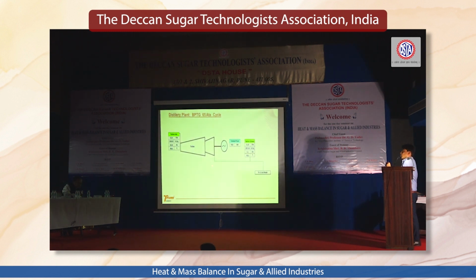So during off-season scenario, when we go for seasonal operation, we extract the maximum amount of steam, almost 80 to 90%, in controlled extraction. The flow to the cooling condenser is only 10 to 15%. So 70% of the latent heat of the steam water is not sent to the cooling tower, we use it for the process. So with respect to seasonal operation versus back pressure operation, efficiency is always on the higher side, 70% to 90%.